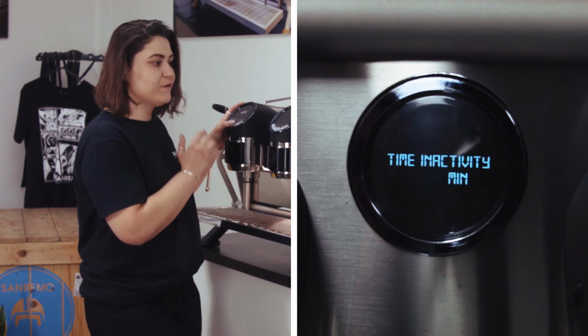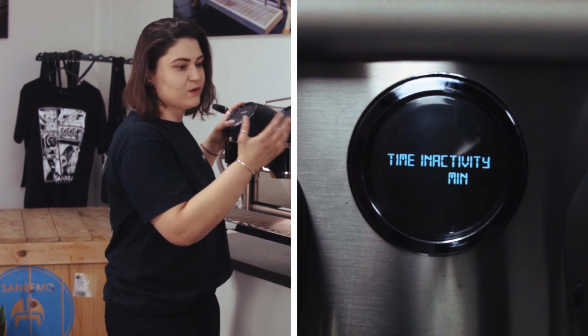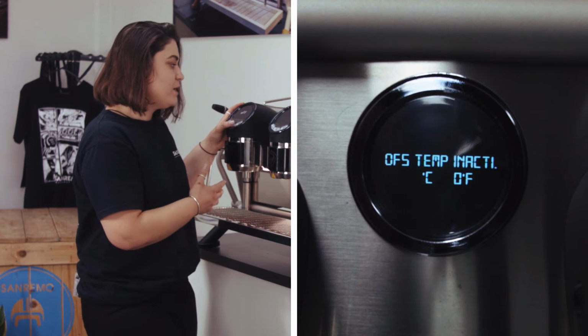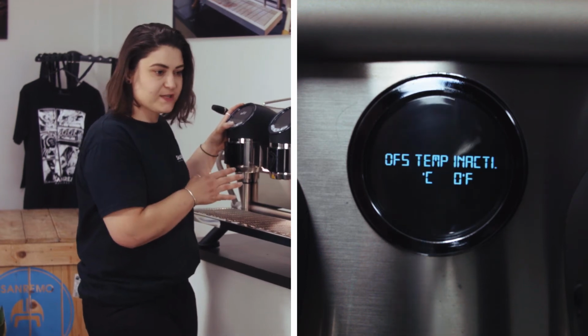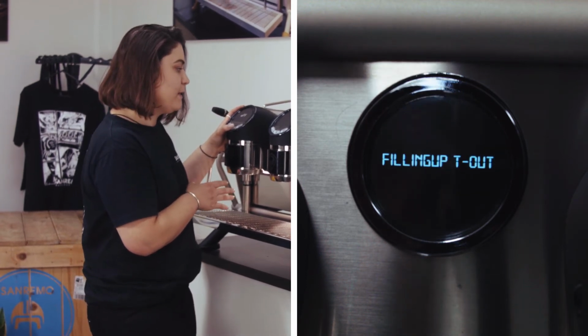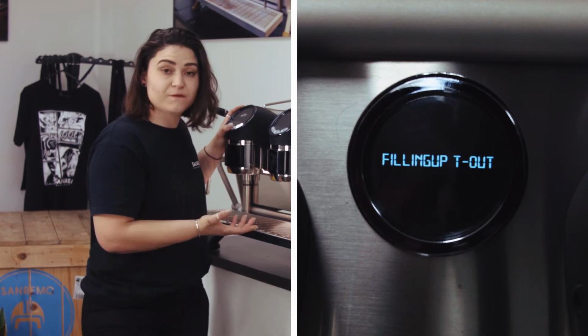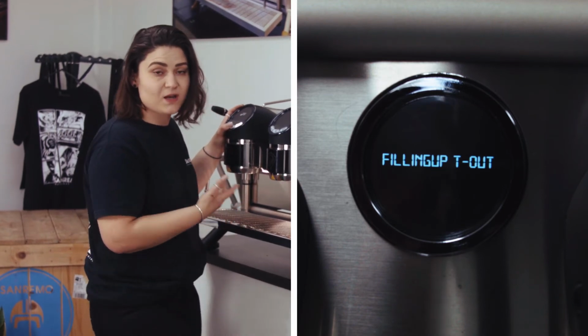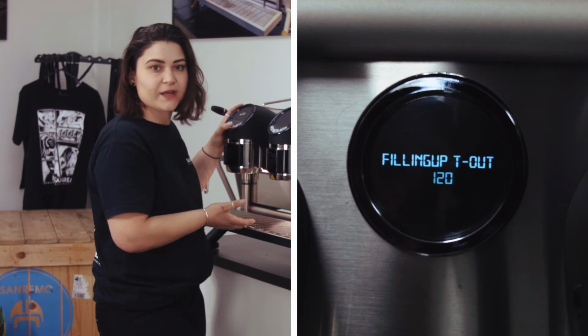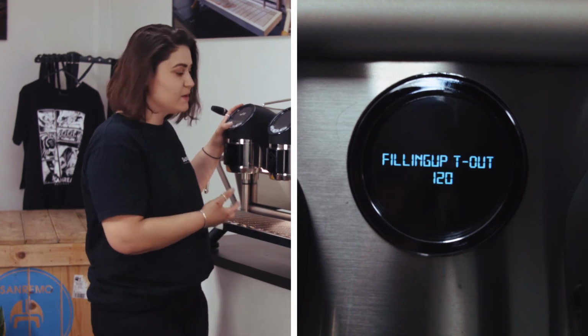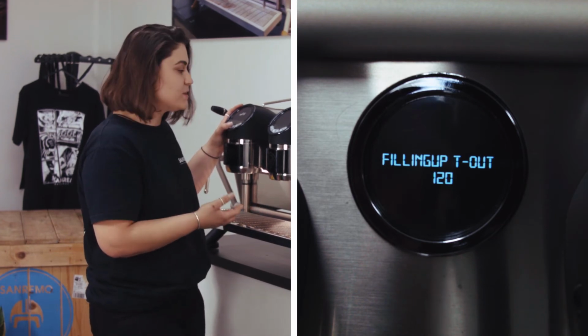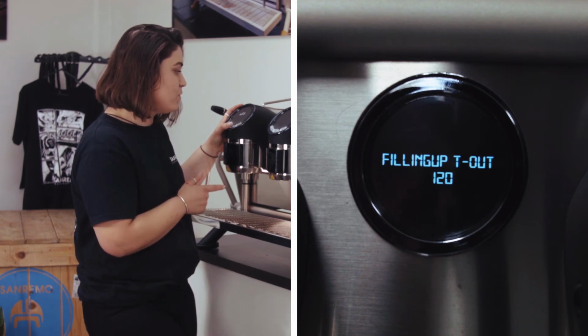Time inactivity. So if the machine's not being used in 2 minutes, it goes into a time and activity mode. Offset temperatures. So you can put offsets on your temps if you like, if you need it. Filling up timeout. If the machine's not filled within a minute 20, it will time itself out and say, I'm not getting enough water, please check the water. So it saves you elements from burning and all that sort of stuff. So yeah, that's what that function's for.